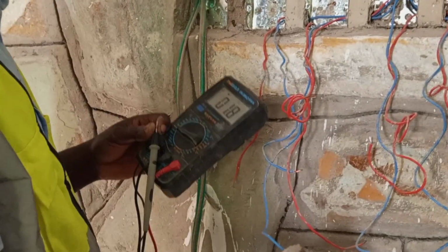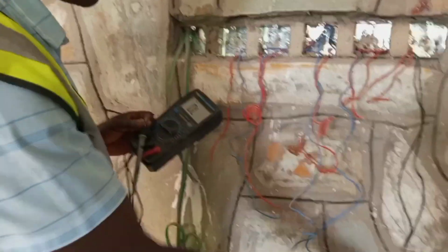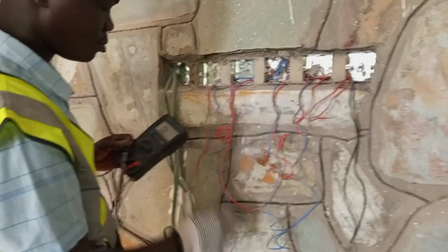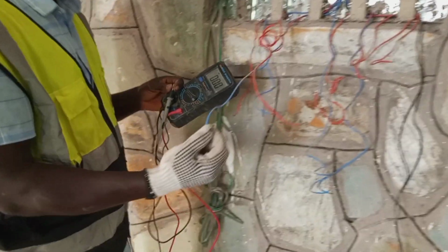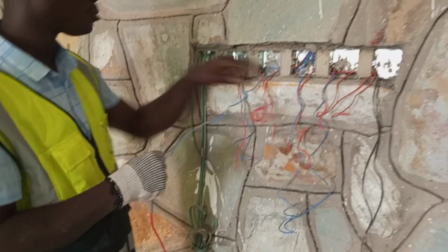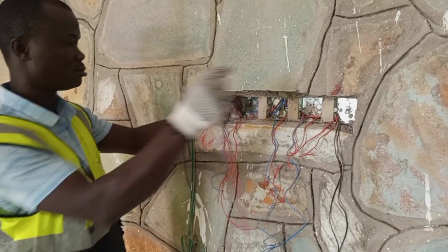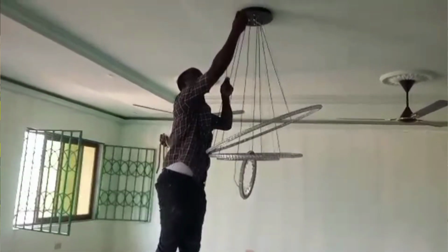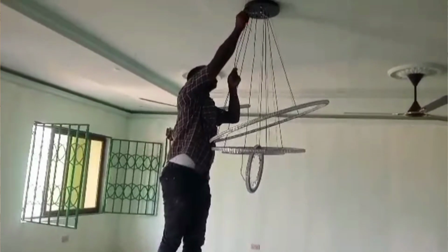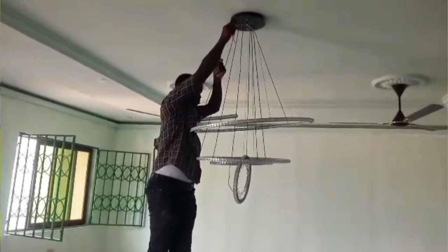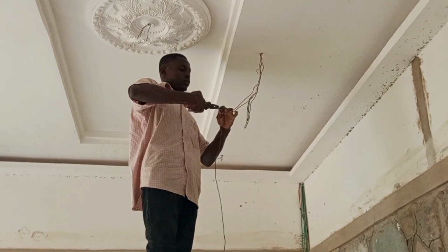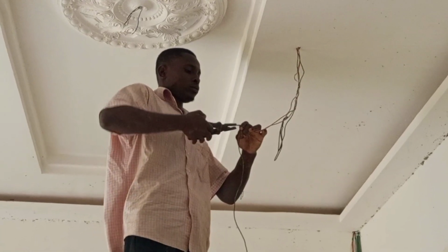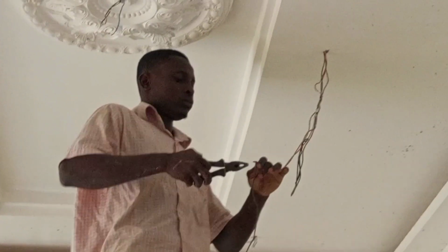then the best way to identify them is to do a continuity test. If you're able to do this test properly and you have fixed your switches and your lights and your fans, if any of those lights or fans are not working, you are now sure that it is not as a result of your wiring, but it could be as a result of the load, the particular lamp or the particular fan that you are fixing. So by the time you finish fixing your switches, your sockets, your lights, and your fans, you would have already done polarity test and then continuity test.